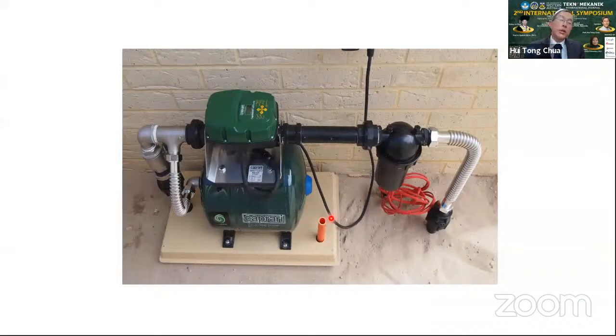So this is the motor and the control module for the submersible pump, and the motor rating is 900 watts. So in terms of energy audit, the power consumed by the submersible pump is included in our energy audit to arrive at the coefficient of performance of the ground source heat pump, which I shall report later.